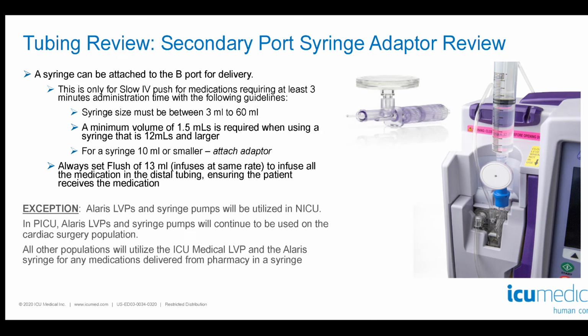A syringe can be attached to the B port for delivery. This is only for slow IV push medications requiring at least 3 minutes administration time with the following guidelines. The syringe size must be between 3 mils to 60 mils. A minimum volume of 1.5 mils is required when using a syringe that is 12 mils or larger. And for a syringe 10 mils or smaller, you must attach an adapter. See the picture to the right. You also must always flush with 13 mils, which infuses at the same rate, to infuse all the medication in the distal tubing, ensuring the patient receives the medication.